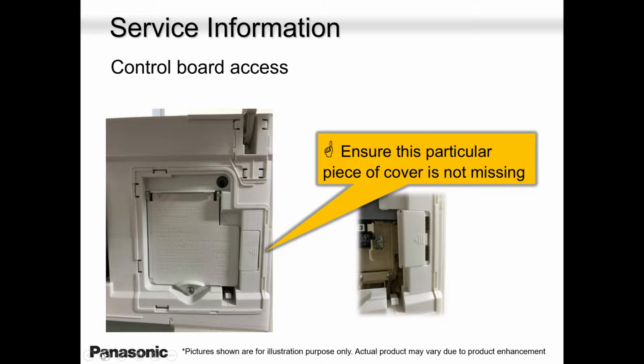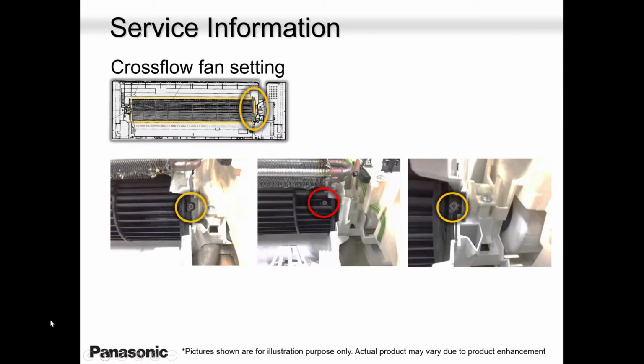Sometimes there is no voltage. Why? Because the outside unit has a problem, and for some reason it's not sending voltage inside. It's not complicated, guys. Please remember, repairing, servicing, maintaining a heat pump is not complicated. It's very simple. If at all you have to remove the blower wheel, remember on the right hand side, when you're facing the indoor unit, on the right hand side over there is where the screw is. You open up that screw, you slide this coil slightly up, and the blower wheel comes out.